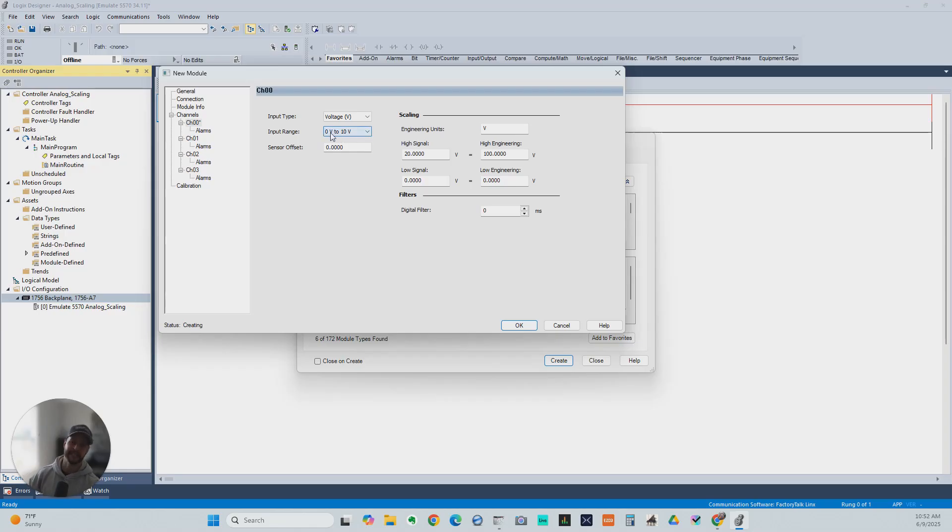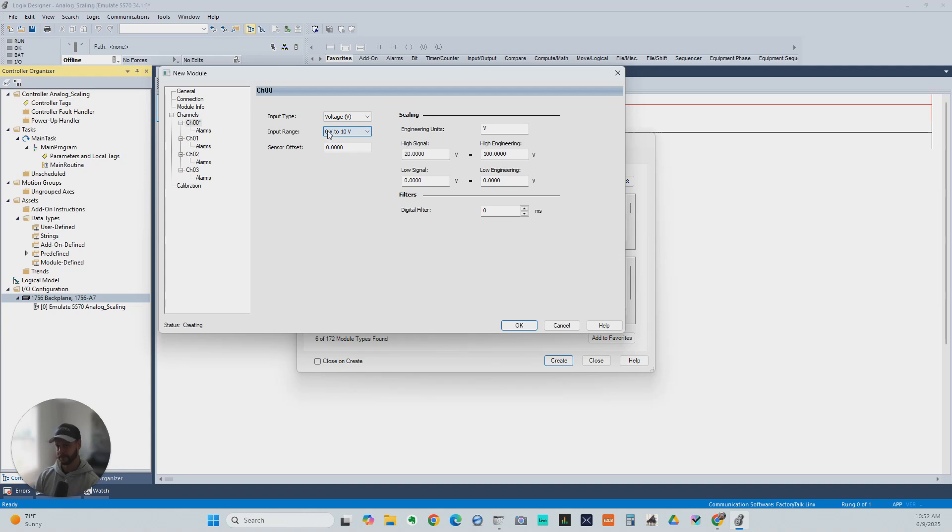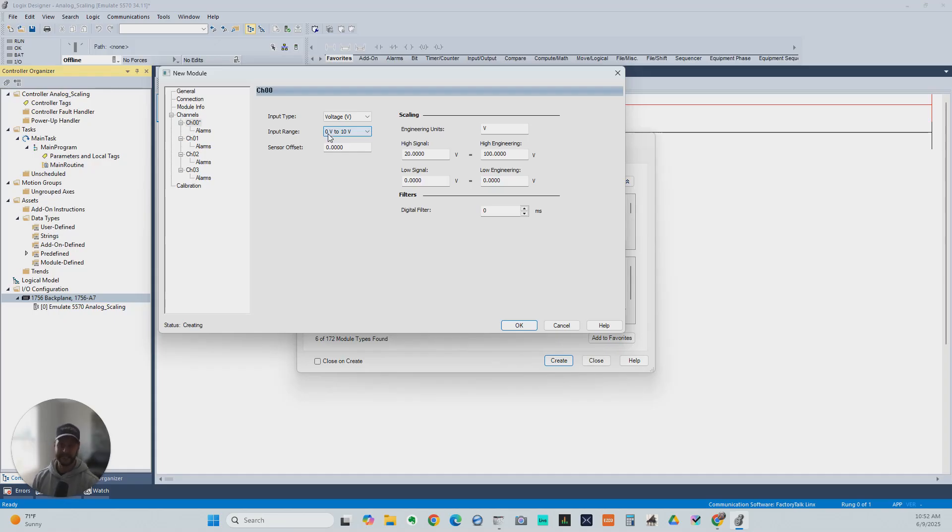normally you would expect something like 0 to 10 volts to be mapped to 0 to 200 gallons. So if the PLC's seen 0 volts, then that tank has nothing in it. If it's seen 5 volts or 50%, then that tank is half full or 100 gallons.